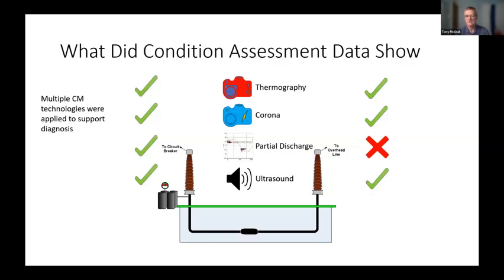So it's important to know that with partial discharge, it can be intermittent. It can have a characteristic where it appears for a while and disappears, and it depends on the load on the cable. So we have to be very wary of just automatically saying the problem is definitely exactly where we think it is. But we have very good information. The DGA in the cable is high. The partial discharge sensing shows a problem in that area. We've got 2 independent tests. We're going to go and do something. Next one, please. So diagnosis, we've got a problem in the line side cable sealing end. 2 independent tests. Next one, please.